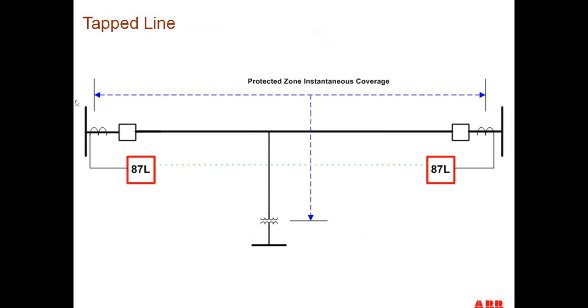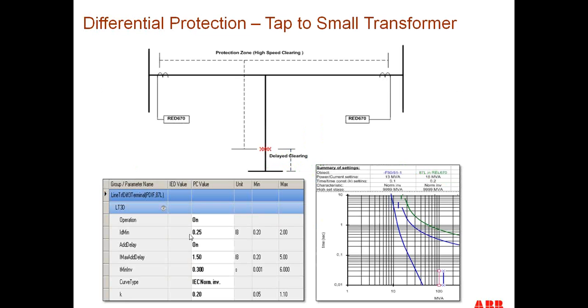So that's kind of shown here. In that particular case, we have full instantaneous coverage for the entire line section, plus down to the transformer tap and the transformer, and any faults below this level will cause a time delay operation of the relay. So it coordinates with the relay at the low side breaker down here. It looks kind of like this, where we can actually choose an ID min, and we can choose a curve that we can coordinate with, so that we coordinate the delayed clearing of any fault down here to let the overcurrent element on the tap operate first before we operate. So we have instantaneous clearing in this particular area, and then time delay clearing in this area down here, based on the curve that we choose.